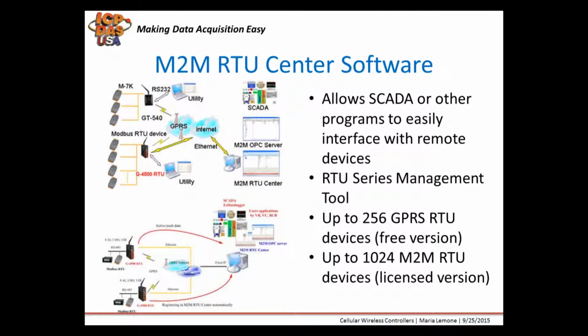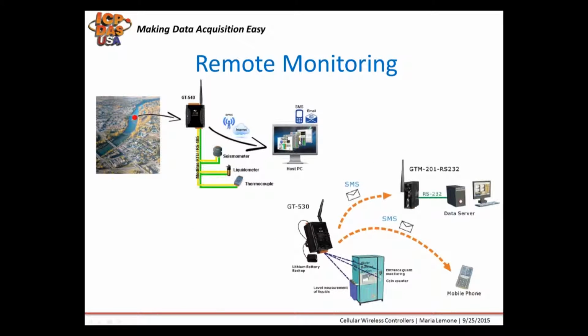M2M RTU Center is free software that we provide for managing up to 256 different M2M RTU devices remotely. We offer a licensed version for supporting up to 1,024 devices. This provides strong core technology for handling data and lets users save the trouble of dealing with large amounts of I/O data. The RTU Center software we provide supports our G4500 series, GT540, and other RTU products that we provide to manage RTU devices remotely. With M2M RTU Center software, you can establish remote systems via OPC client, and your SCADA software can work easily. You don't have to do all the configurations and everything manually.